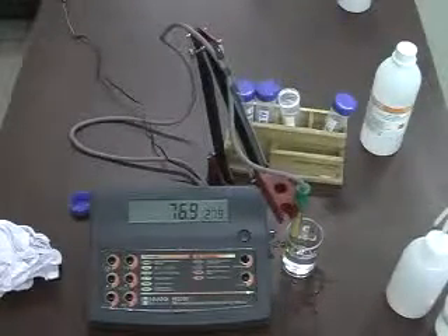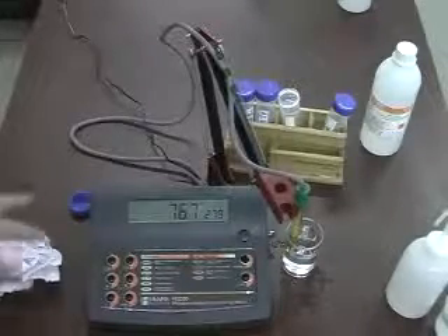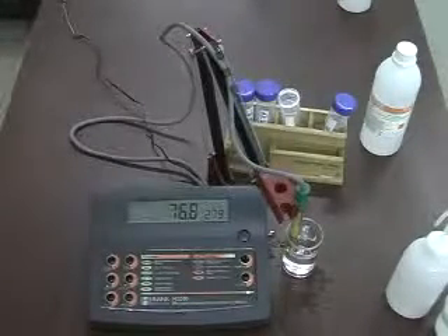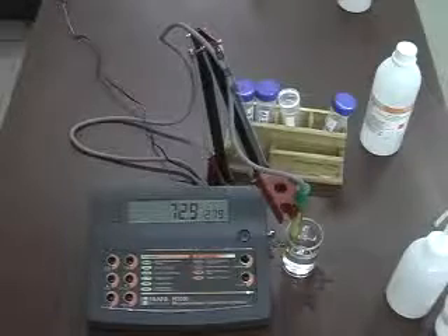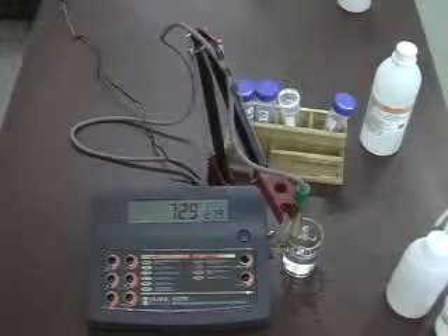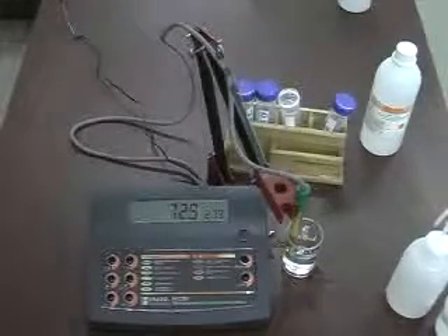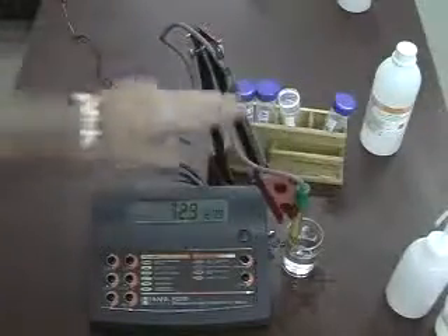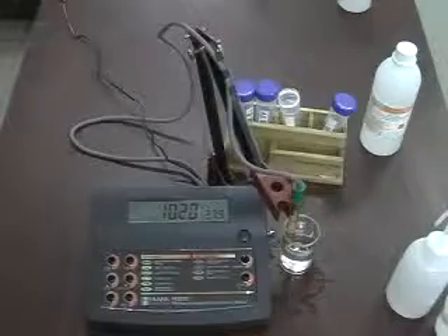Alright, now the probe is placed in the 84 microsiemens solution. The accuracy of the instrument is 1% of that value, which means at 84 microsiemens I would expect it can be up to an 8.4 difference. And I will show you, just by lowering this down into the solution, we can actually change the value a little bit because of getting around the rings.